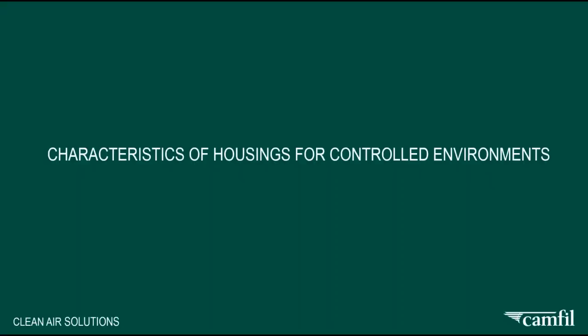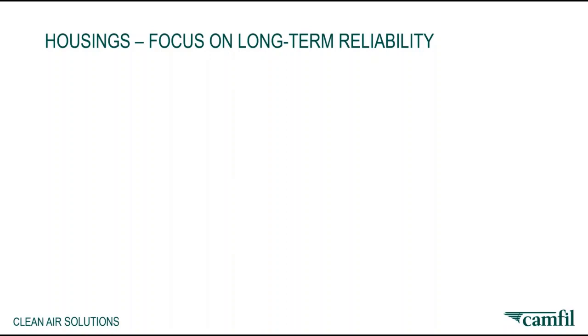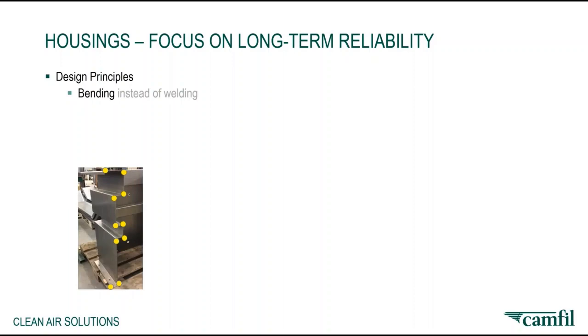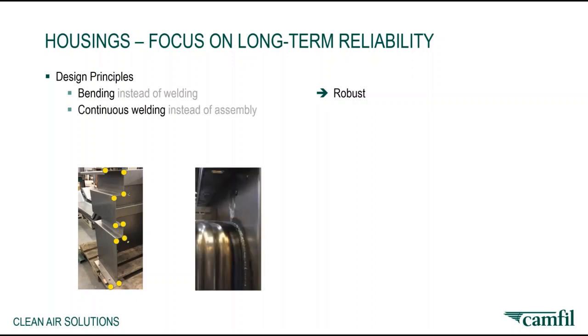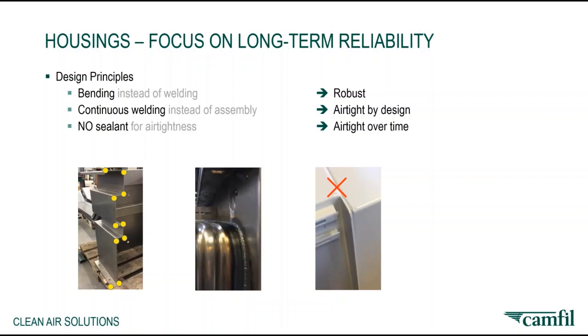If operational quality control is adapted according to the product, there still are some global characteristics of housings for controlled environments that are to us globally valid design principles. And the overall focus here is clearly on long-term reliability, as we think it should be for housings in controlled or otherwise safety-critical environments. Those principles are, number one, we use bending metal forming instead of welding or other forms of assembly whenever possible. That gives us sometimes complex parts, but always mechanically robust parts. Number two, if we have to, we use continuous welding for the containment barrier. This means the housing will be airtight by design. And since there will be no sealant for airtightness, that means it will remain airtight over time, whereas sealants will end up drying out and then give you issues.